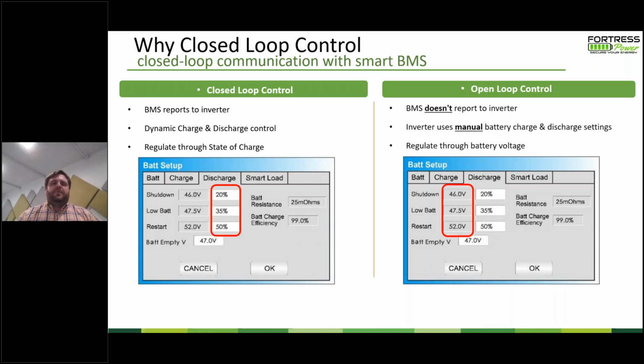What that means, though, is from the 20% mark of the battery all the way up to the 80% mark of the battery, the voltage is very stable, and so it's hard to convert voltage into a percentage. The way you convert voltage into a percentage is you actually count the energy coming out of the battery at that voltage level and make a guess as to the state of charge. And the only way to do that accurately is to have a computer on the battery itself making that calculation. In the past, inverter manufacturers have used their inverter systems to make that calculation, but it's not accurate, and it's not as accurate as if the BMS is doing that calculation itself on the battery.